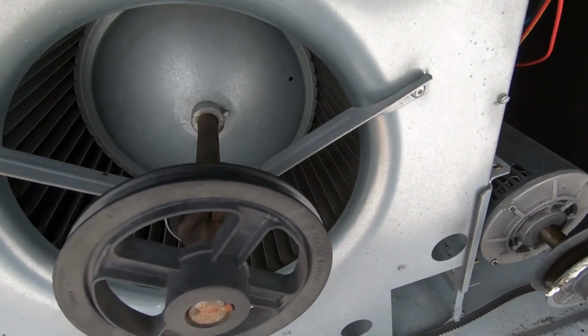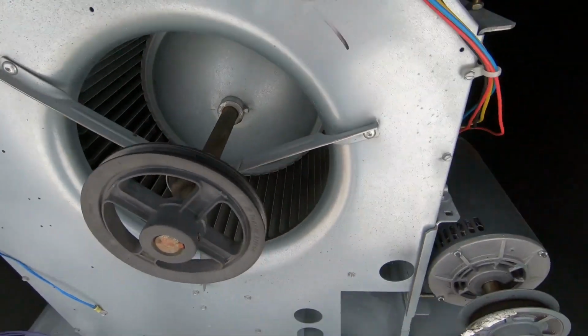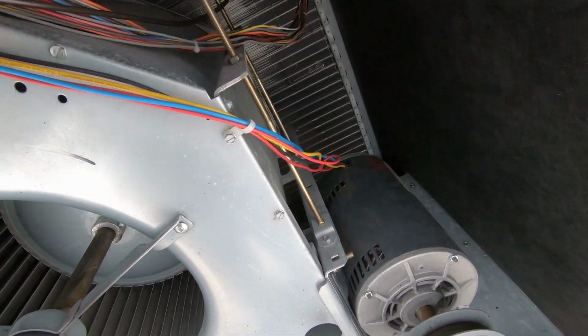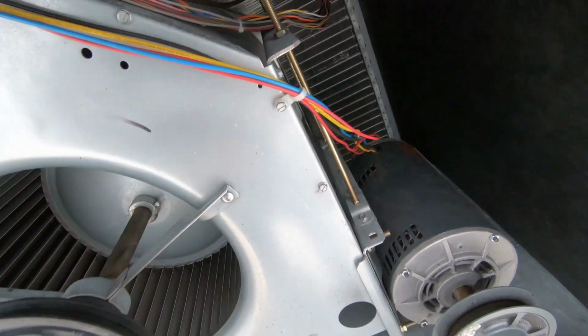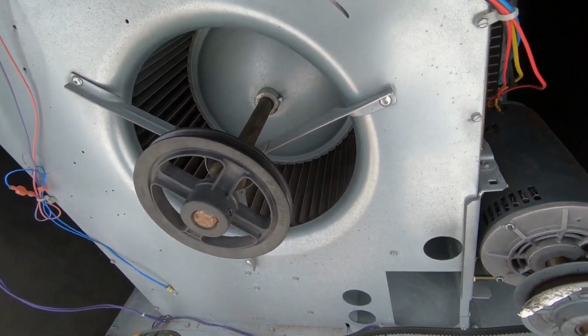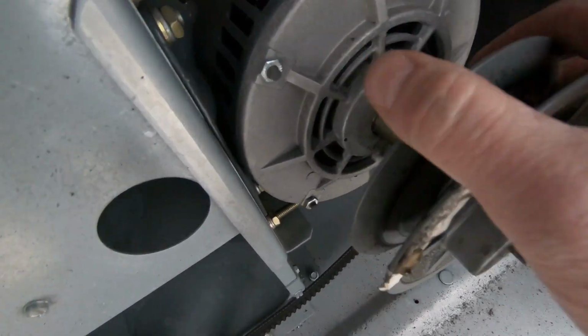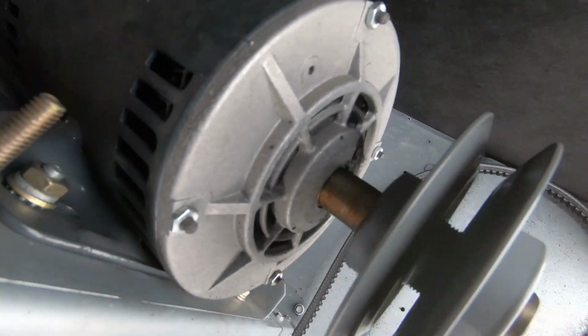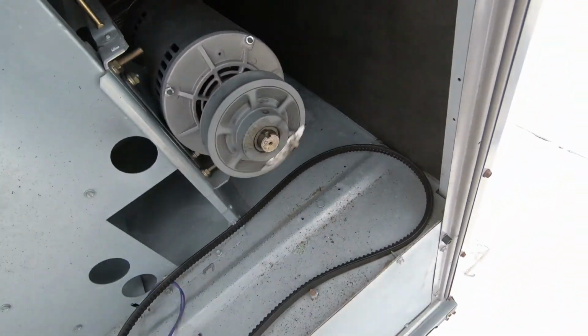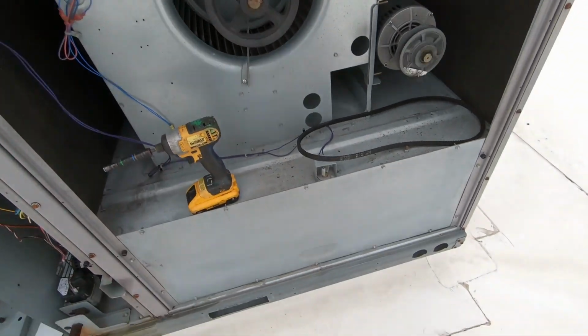All right, well, the wiring is nice and flexible. No brittleness to it. The other one is very brittle. But the motor bearings in it are sounding not good. We'll recommend a motor on that one.